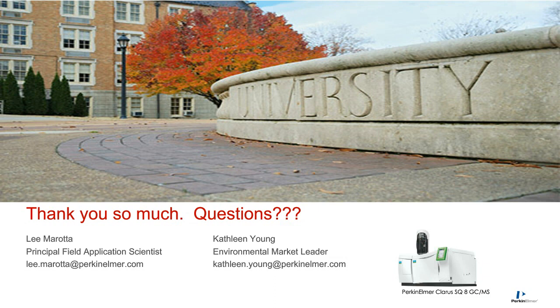I was away from my lab for 5 months, and I came back, and my tune was bang on. I usually say, well, you have tuning criteria to meet. So if you're meeting BFB and DFTPP, I would not touch tune, only check to make sure that you're still mass calibrated. You could do that by looking at your standard and seeing if the mass moved when you bring up your spectrum.